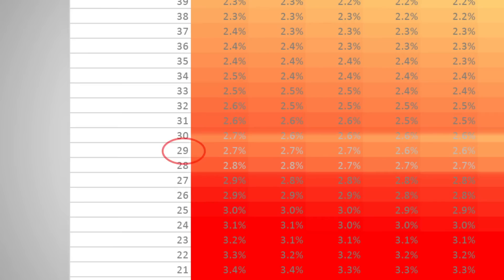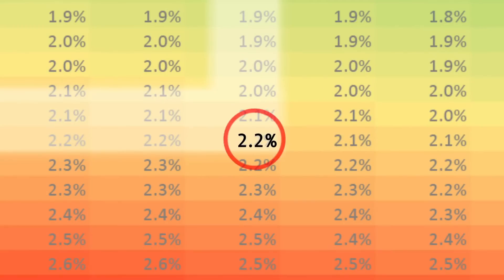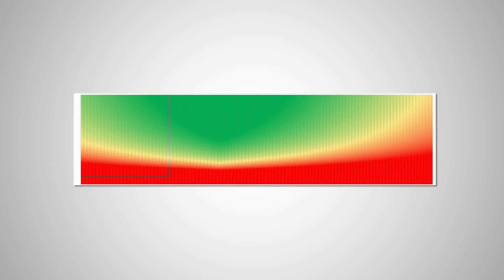This data point shows 29 percent of full scale at 40 degrees Celsius, and tells us that we are at 2.2 percent allowed error in the yellow transition area.